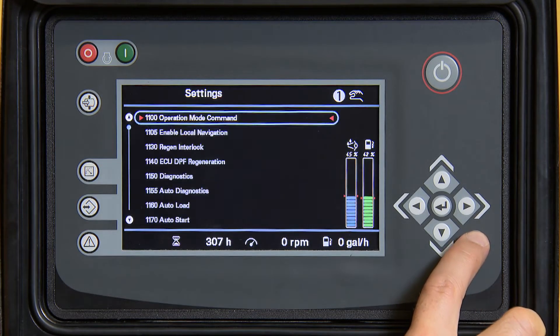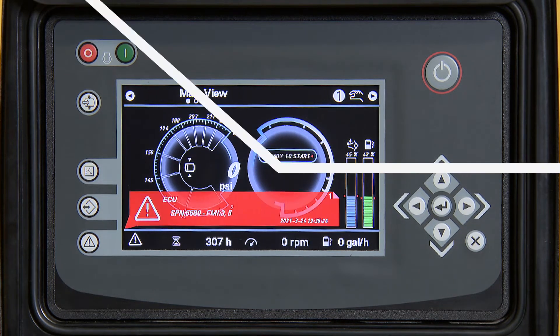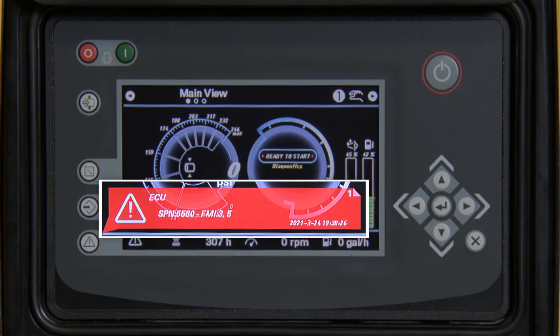At this point, the controller will read or look for any fault codes being broadcast across the CAN from the engine ECU. This may take a couple of minutes. As you can see, we have one fault code SPN 5580 FMI3 with five occurrences.